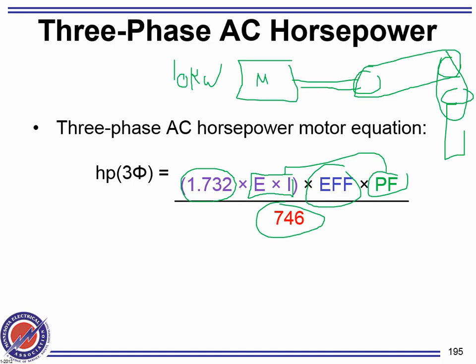To help you with the following. Can anybody tell me what's the only thing that could change if this was single phase? I need you to pinpoint one thing that will change. If that was single phase, what's the only thing that would change? Perfect. Same equation. Okay, second thing. I would like you guys to pinpoint the two things that will change if that was a DC motor. But one of them is already crossed, right? That's crossed because DC doesn't have 1.732. Does the DC have power factor? No, no power factor. Gentlemen, here's the formula for DC.